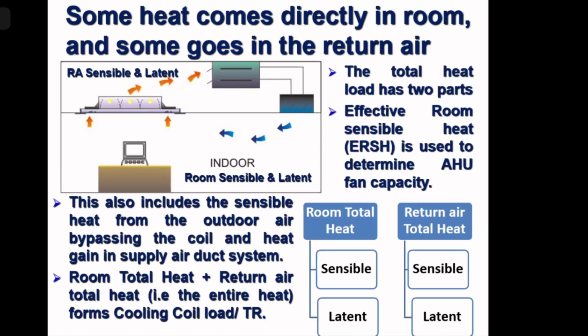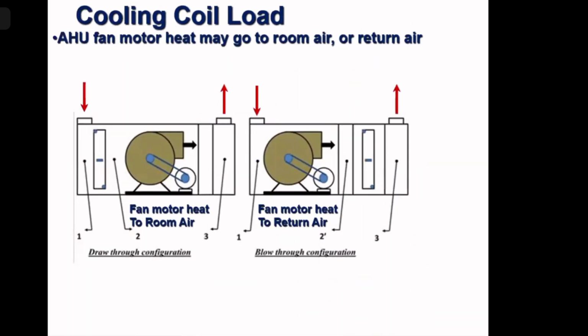Room total heat plus room return air total heat will determine the cooling coil size and tonnage of the plant. That's what we told already. So when you determine the size of your air conditioning plant, that is tonnage of the air conditioning plant, you have to consider all the heat. Next. Now, location of the fan motor.